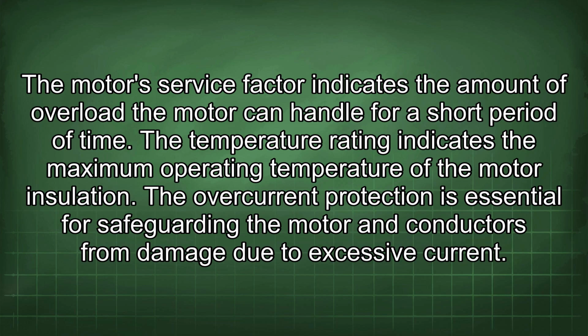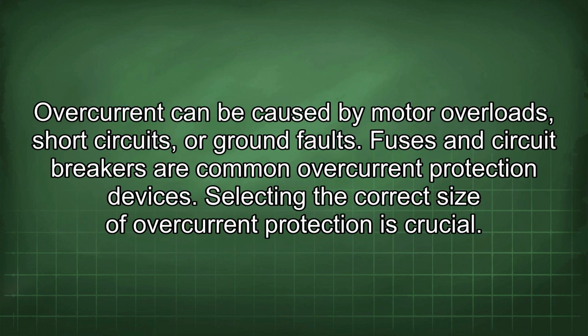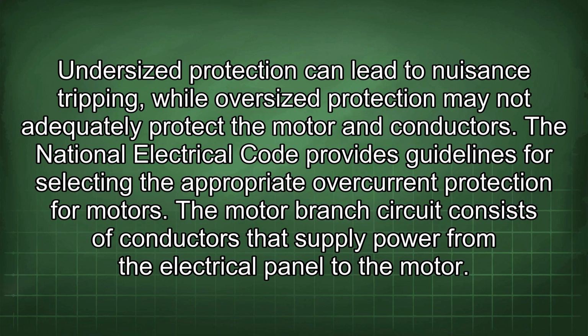Overcurrent protection is essential for safeguarding the motor and conductors from damage due to excessive current. Overcurrent can be caused by motor overloads, short circuits, or ground faults. Fuses and circuit breakers are common overcurrent protection devices. Selecting the correct size of overcurrent protection is crucial. Undersized protection can lead to nuisance tripping, while oversized protection may not adequately protect the motor and conductors. The National Electrical Code provides guidelines for selecting the appropriate overcurrent protection for motors.